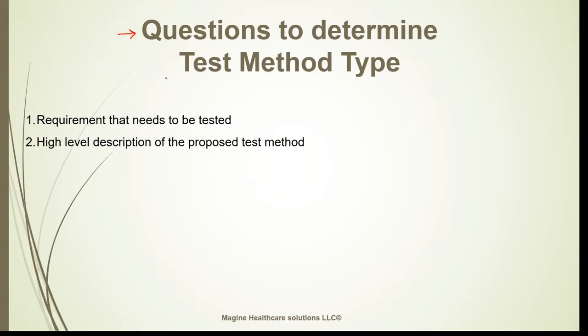The second question is a high-level description of the proposed test method. For example: length of a plastic tube using a calibrated ruler, resistance measurement of an electric wire using a multimeter, go/no-go measurements using a pin, and presence of foreign material on a sterile package. These are high-level descriptions of the proposed test method.